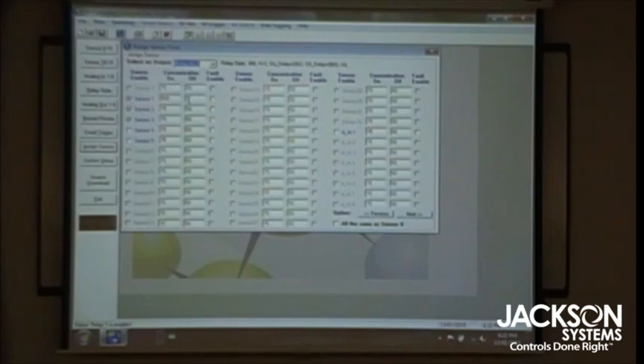And what's neat with this is that you can save the program and you can print it out. So if somebody comes to ask you, how the heck do you have this programmed? You can show them, okay, sensors 1, 2, 3, and 4 are addressed to relay 1, and it turns on at 20 ppm and off at 5. So you actually have a printout of all the parameters, and you can also store it on your hard drive or transfer it to a thumb drive on your laptop. So very, very flexible software with the unit.